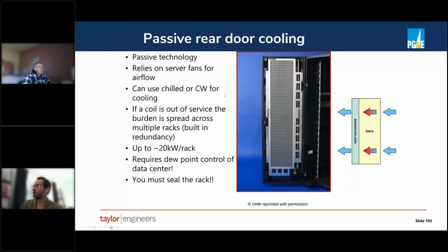The other common strategy is something called a rear door, which has two options. One is a passive and the other is an active. We'll start with passive rear door, and it's called a passive rear door because it relies on the fans that are integral to the servers to move airflow across the rear door coil. So we're looking at a rack. The air is coming in again from the cold aisle side. The rack is pulling the air through, and then it's pushing it through the heat exchanger, which lives on the back side of the server cabinet. So the air effectively comes back out of the rack again at the cold aisle temperature.